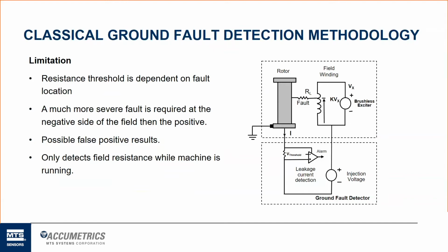So that could potentially lead to possible false positive ground fault results. We've had customers air their frustration on that, where they thought their detector measured a low ground fault, and they shut the machine down and did further testing, megger or hipot testing, and discovered that that wasn't the case. It also only detects field resistance while the machine is running. And of course, in most cases, there are those mechanical and physical limitations from either the optical sensor or the brush rigging, slip ring assembly.